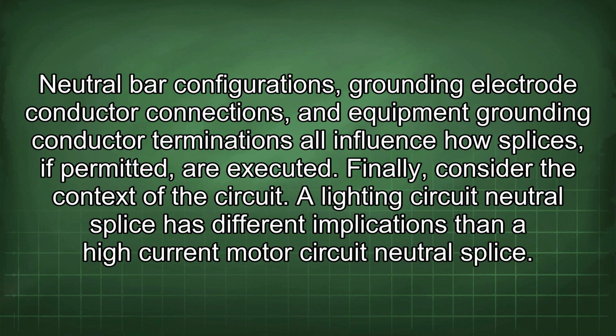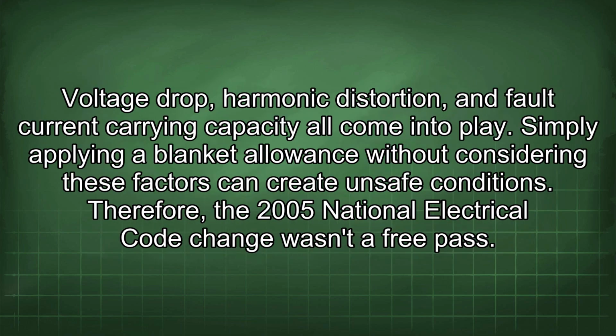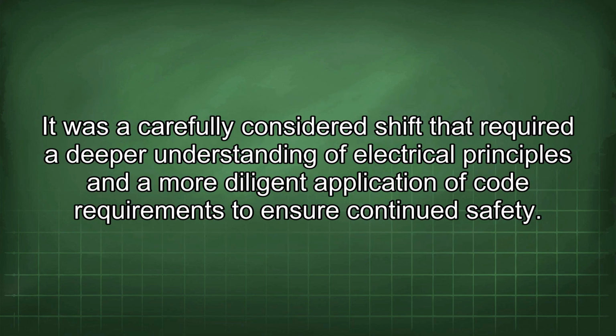Finally, consider the context of the circuit. A lighting circuit neutral splice has different implications than a high current motor circuit neutral splice. Voltage drop, harmonic distortion, and fault current carrying capacity all come into play. Simply applying a blanket allowance without considering these factors can create unsafe conditions. Therefore, the 2005 National Electrical Code change wasn't a free pass. It was a carefully considered shift that required a deeper understanding of electrical principles and a more diligent application of code requirements to ensure continued safety.